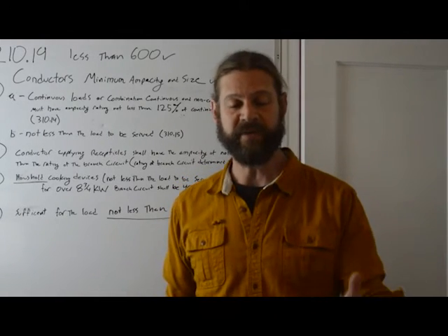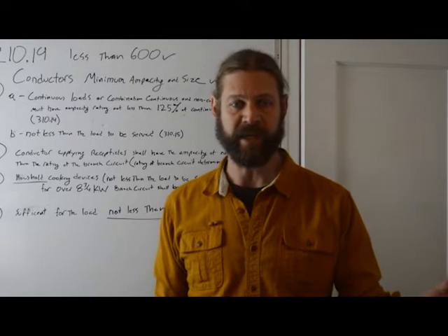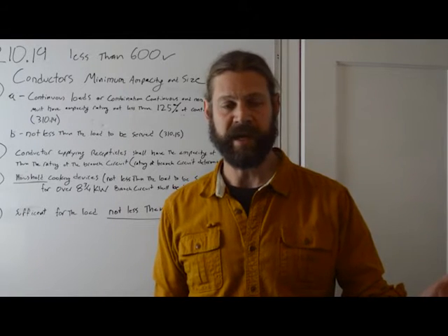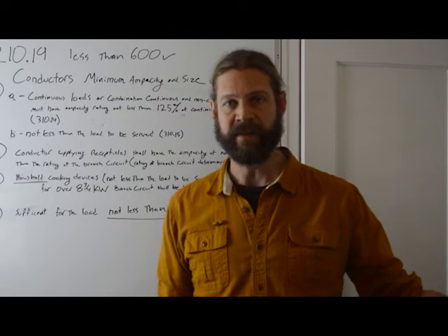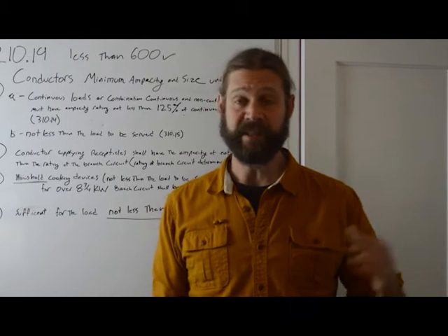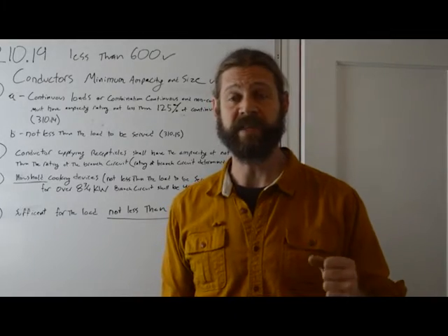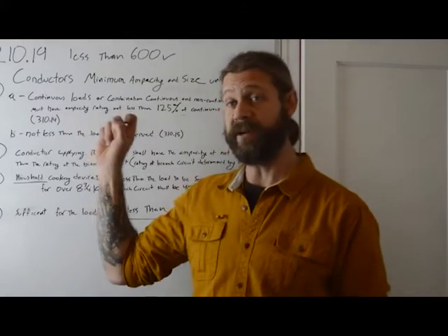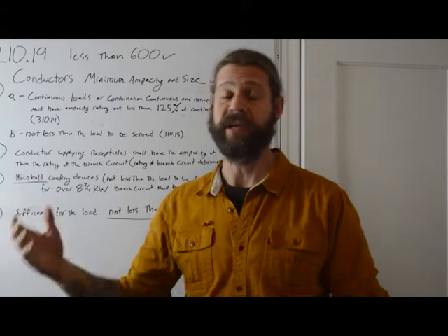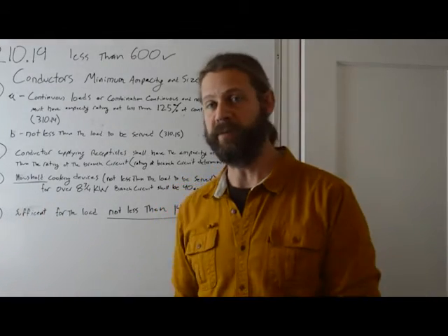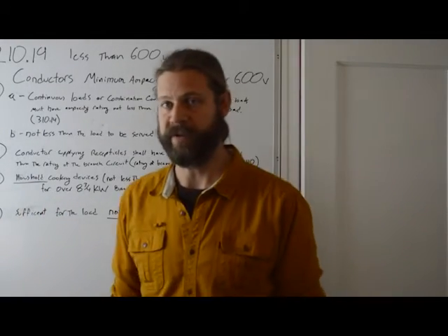We actually did a video where we installed a space heater in a client's garage, and the space heater rating was 30 amps, but we didn't run 30 amp wire and we didn't put a 30 amp breaker in it because you actually have to size that wire and that breaker at 125% of that continuous load. That heater is a continuous load. It requires that 125% correction factor.